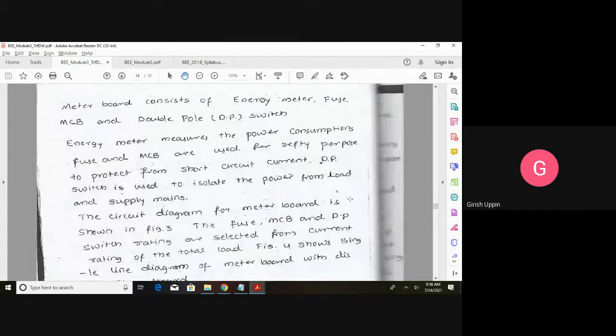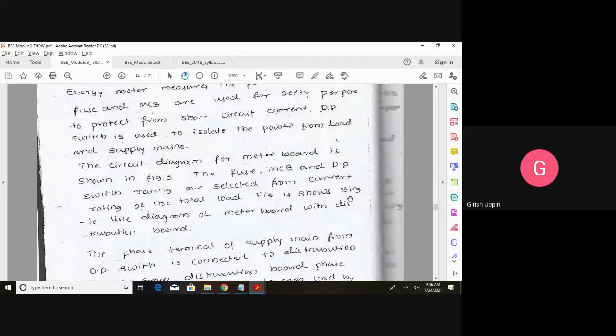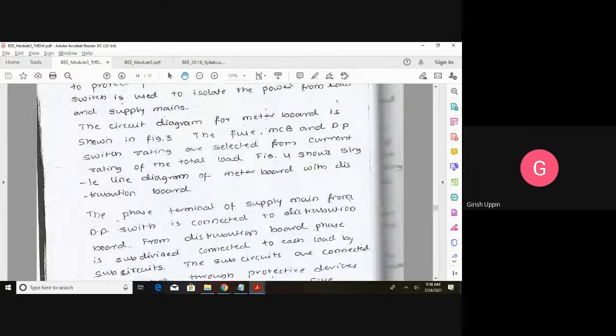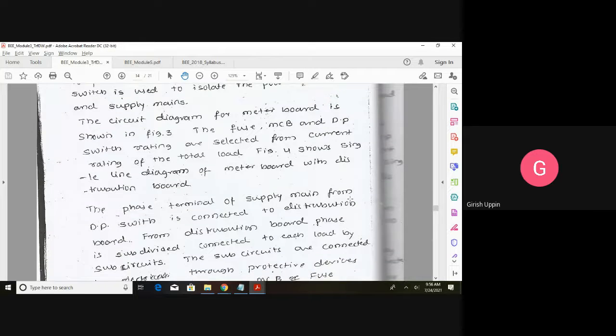Okay, the meter board consists of the energy meter, fuse, MCB, and double pole switch. The energy meter measures the power consumption. Fuse and MCB are used for safety purposes to protect from short circuit current. The DP switch is used to isolate the power from the load and supply mains. The circuit diagram for the meter board is what we already saw. The fuse, MCB and DP switch ratings are selected from the current rating of the total load. And figure 4 shows the single line diagram which we saw.